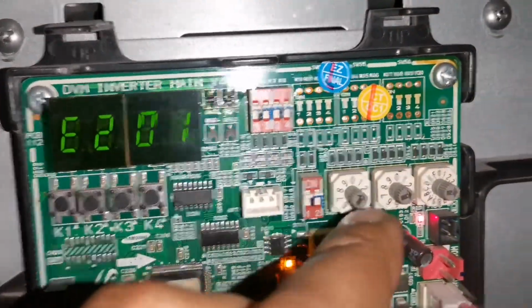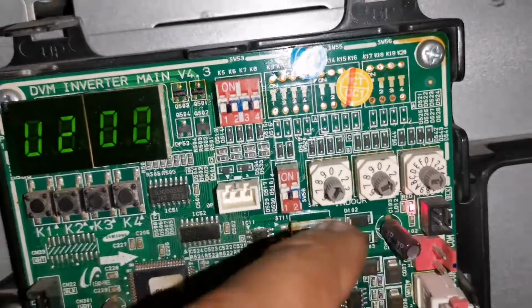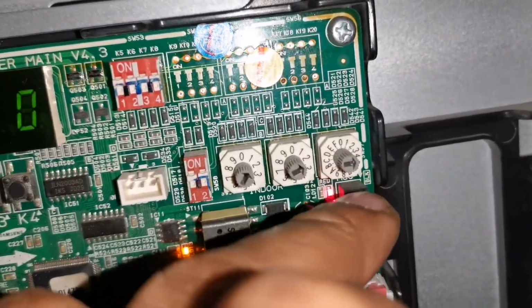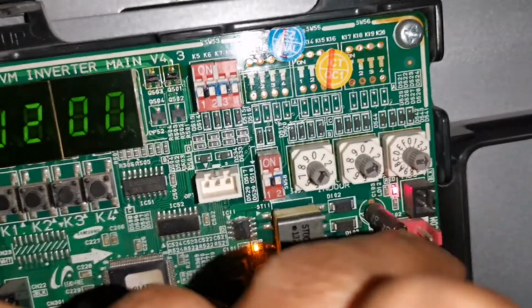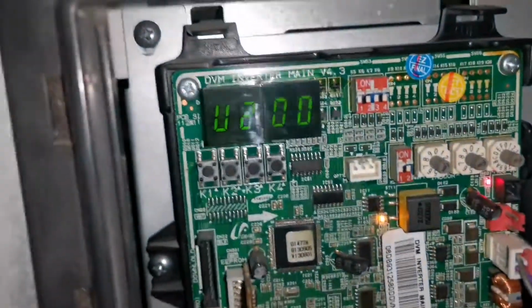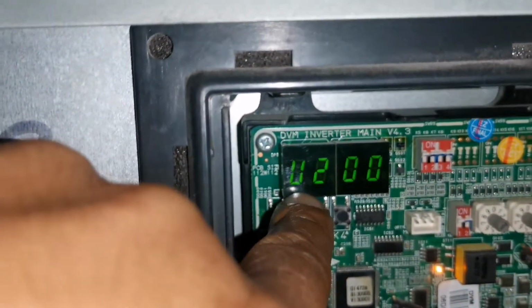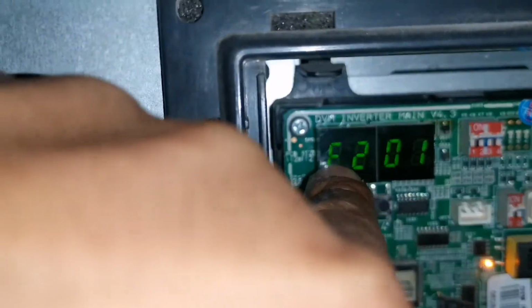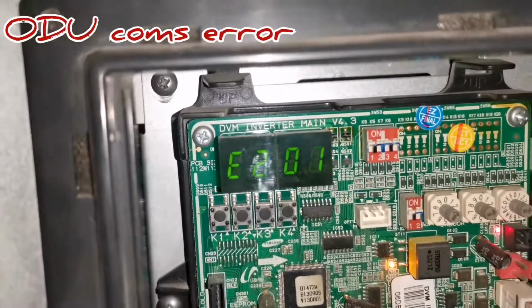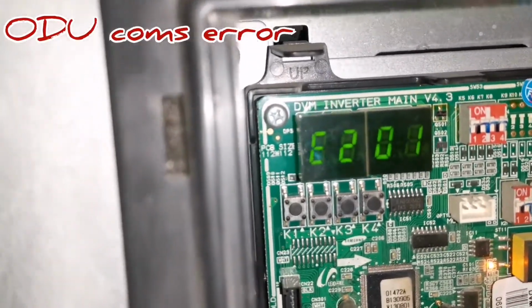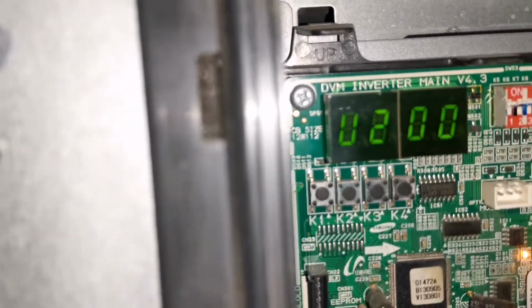Again, we can see here on the dial-up switches, we've got 12 indoors and we've got 4 MCU units, the master control unit, which will be your split boxes. We've got an E201, which is a communication error, but that is because one or a couple of the indoor units are switched off. There's a tenant that moved out, so these communication cables run in a chain loop, so that's why we've got that issue over there. But the system's all pressurized.